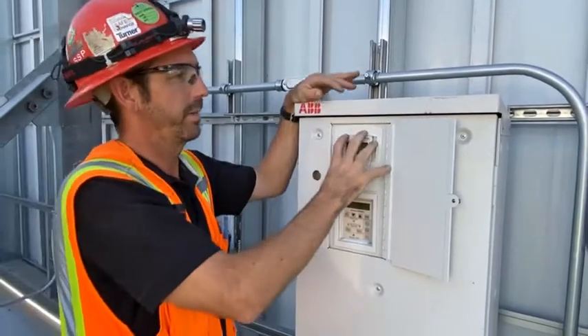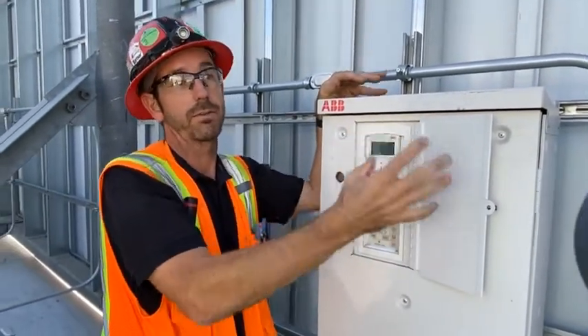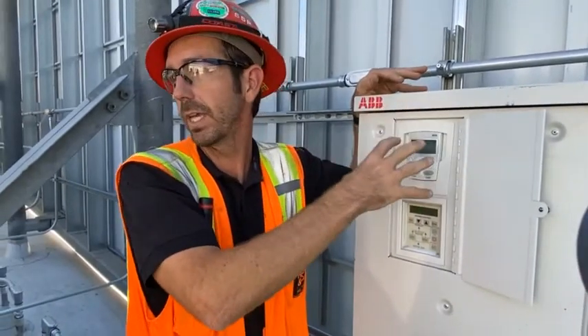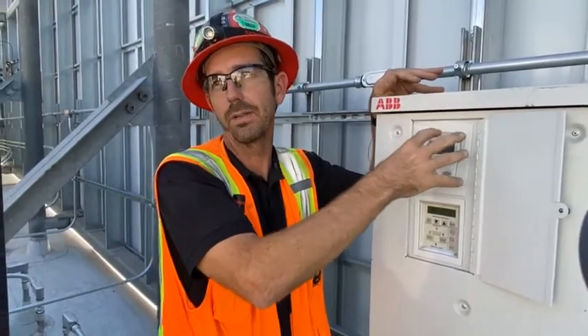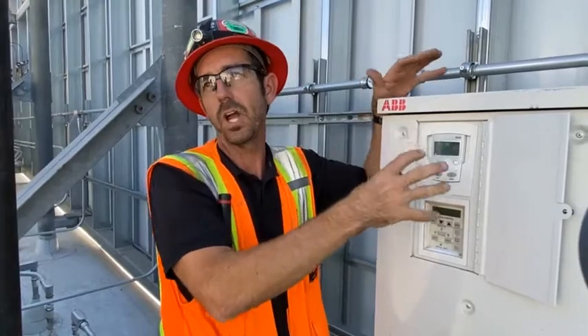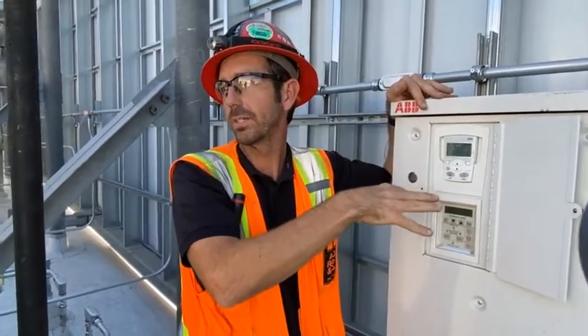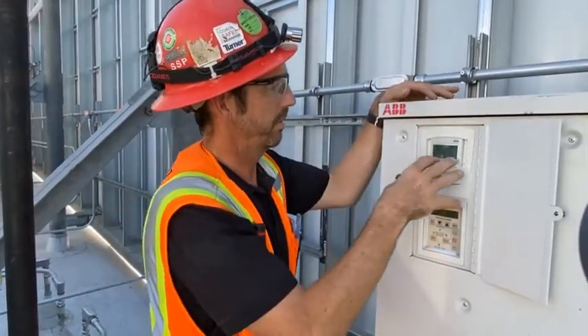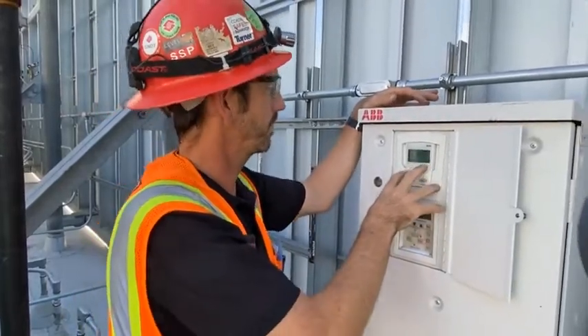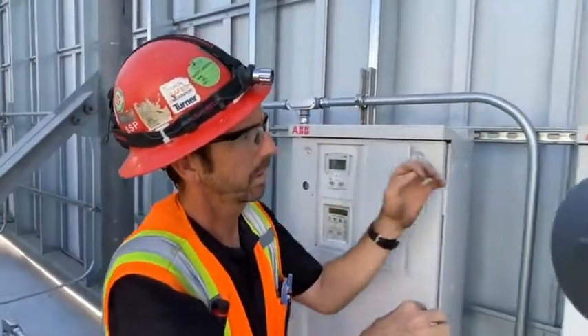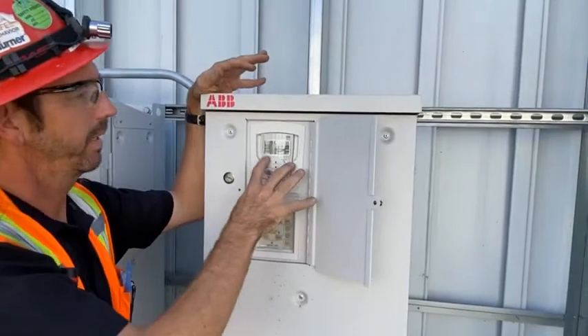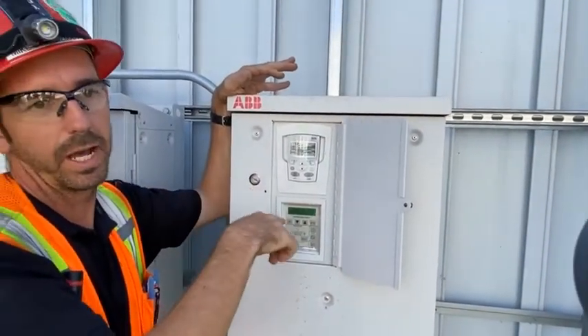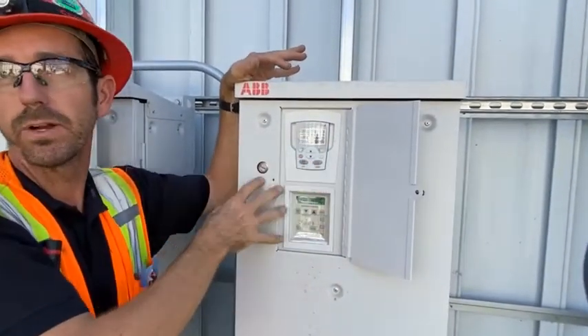So we transfer that instead of having to do changing programming. So when I downloaded that is what I was trying to show you guys. If you have to replace a drive, you could use the old keypad as long as the most current information is downloaded into it. Replace the drive and download that application into the new drive, okay? So now this one has the most current data. And then what we need to do in this keypad, because it came off of that one, is we need to upload the information into this keypad because we already know that this one was right.